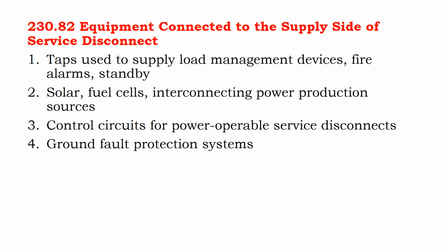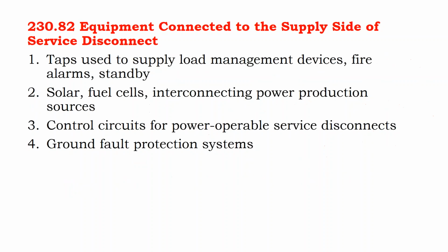And so by the time you want to do a supply side connection at your local office, you call up the permit office and they say, well, we only allow load side connections. You can't do supply side connections for solar. At that point, it really helps to refer them to the National Electrical Code and say, look, if we were doing a whole house generator, how would we interconnect it? Where would we land it? Well, it's that same supply side connection.